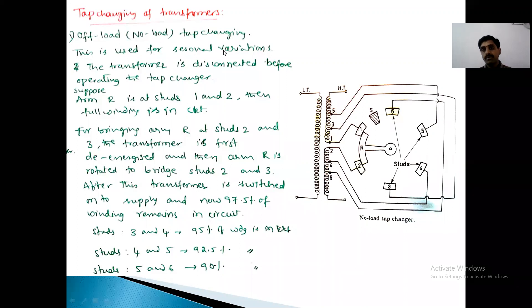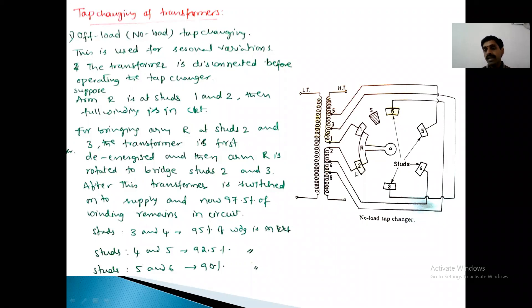This is an offload tap changing transformer, mainly used for seasonal variations. First, the transformer should be de-energized — the supply should be cut. When the arm is at 1 and 2, the full circuit is included. Bring this arm to the 2–3 position with the supply already switched off, then switch on the supply. Again, if you want the tapping at 3–4, switch off the transformer, move the tapping to 3 and 4, then switch on. Like this, we can move this arm between different positions so the number of turns on the secondary can be varied and we get variable voltage.